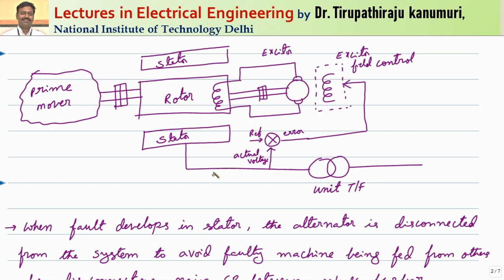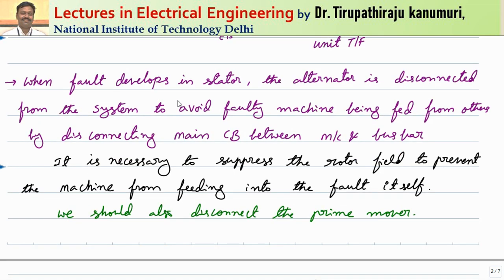For external faults, disconnecting the circuit breaker is sufficient. But for internal faults, only disconnecting the circuit breaker is not sufficient. Along with disconnecting the circuit breaker, we have to remove the excitation system as well as the prime mover. So whenever we want to disconnect the alternator, some associated equipment also needs to be disconnected so that there will be no further problem.